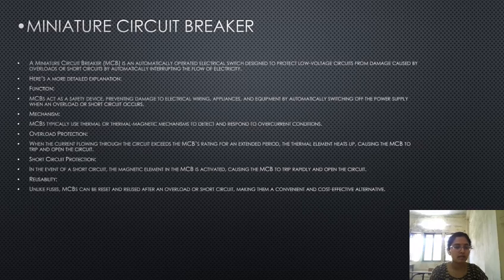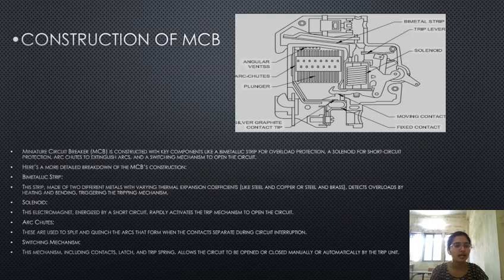Miniature circuit breaker. A miniature circuit breaker is an automatically operated electrical switch designed to protect low voltage circuits from damage caused by overloads or short circuits by automatically interrupting the flow of electricity. Here is a more detailed explanation. Its functions are: MCB acts as a safety device, preventing damage to electrical wiring, appliances, and equipment by automatically switching off the power supply when an overload or short circuit occurs. Its mechanism. MCBs typically use thermal or thermal magnetic mechanism to detect and respond to overcurrent conditions. Construction of MCB. Miniature circuit breaker is constructed with key components like a bimetallic strip for overload protection, a solenoid for short circuit protection, arc chutes to extinguish arcs, and a switching mechanism to open the circuit.